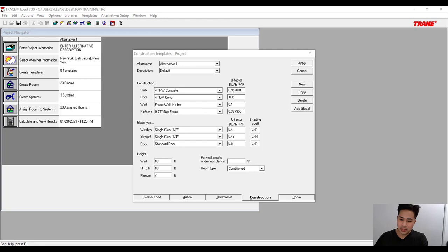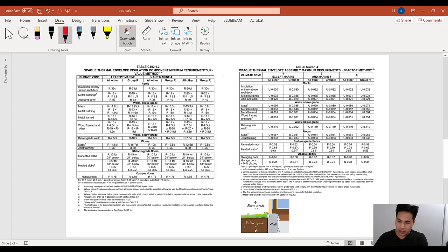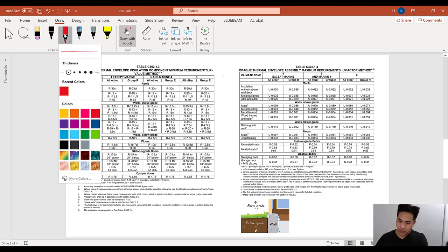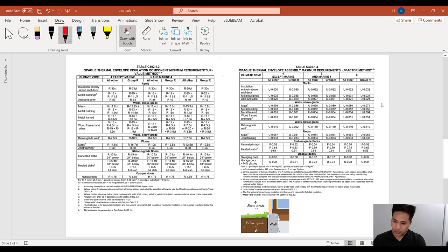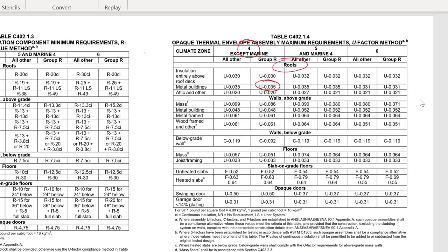For the slab we'll leave it at the default for four-inch heavyweight concrete. For the roof, we need to follow the NYC energy code and use the highest U-value we can find. New York City is in climate zone 4, and the highest value I see is 0.035. There are two columns — Group R and All Others — and we're setting the template to the higher of the two so it can be used for both residential and office buildings.